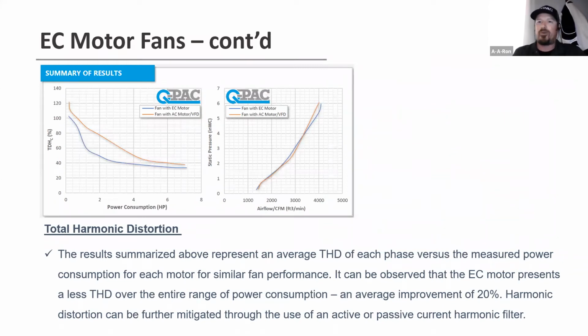And then one of the misconceptions that we hear a lot for EC technology is total harmonic distortion. Normally what I tell customers is that if your current system has a VFD in place, then you don't need an active or a passive filter to lower that harmonic distortion. ECs tend to be about 15 to 20% less on a harmonic scale than their equivalent VFD counterparts. If you want to eliminate it altogether, you would need an active filter. Those tend to be pretty expensive, and I only recommend those for places like hospitals that are putting things near MRI, CAT scan machines, data centers with highly sensitive servers and things like that. In most cases, those are already on the prints or probably already installed anyway, because both the VFDs and the EC technology use 6-pulse inverters. So you'll find those on the 5th and 7th registers to eliminate those.